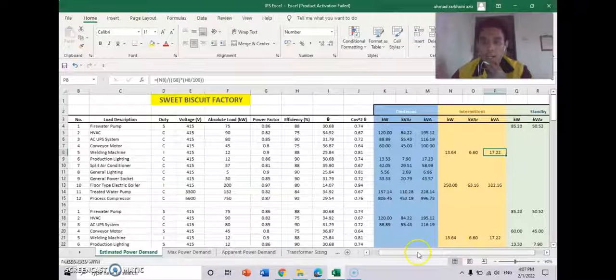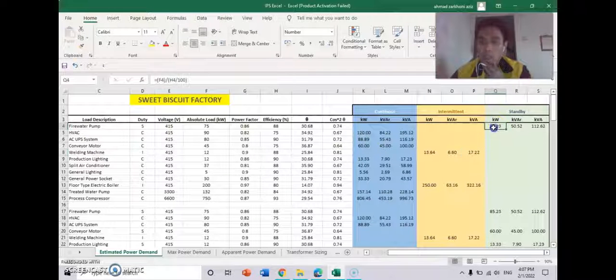For standby, for example the fire water pump, in kilowatts we use the absolute load value 75 divided by 88 efficiency over 100, so we get 85.23. For kVAR, we use this value 85.23 times the square root of 1 over 0.74 from cos power 2 theta minus 1, so we get 50.52. And for kVA, we also use 85.23 over 0.86 from the power factor times 88 over 100. So we get 112.62. For continuous and intermittent we also use the same formula as standby.